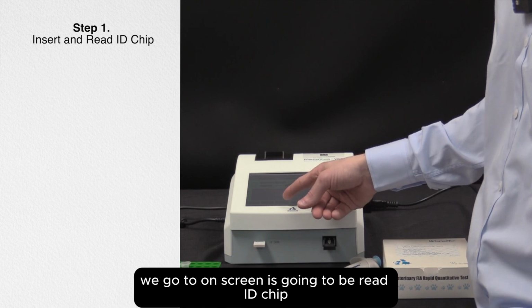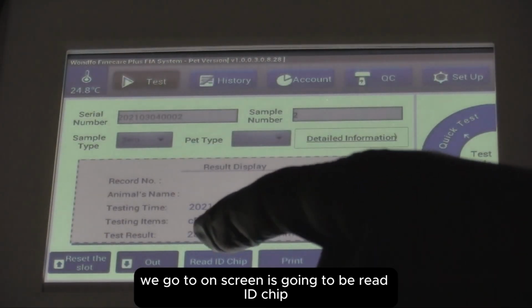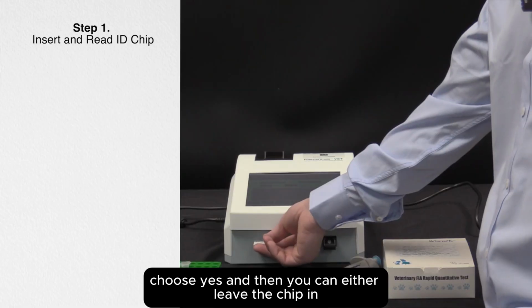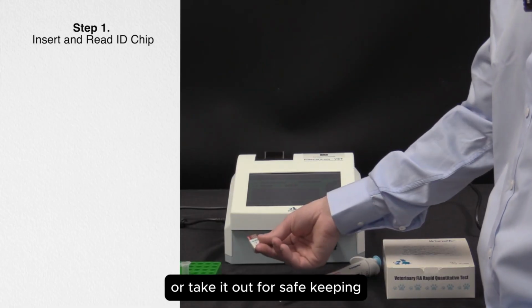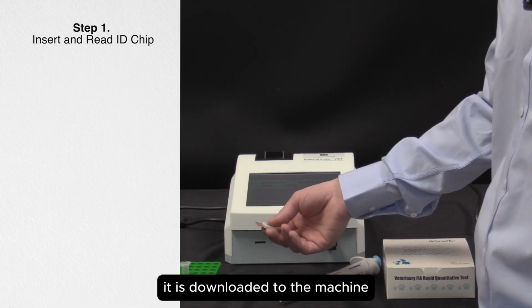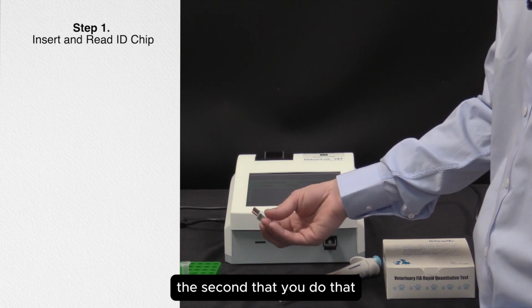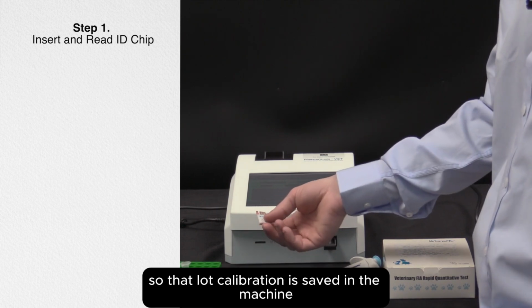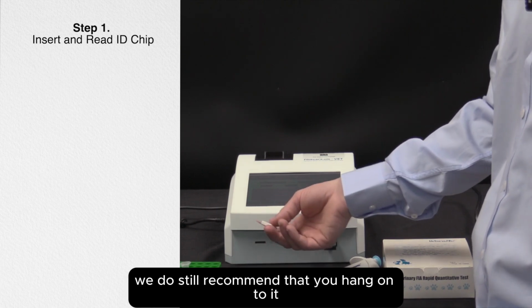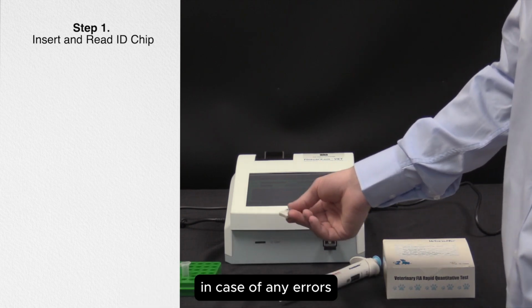Then the next step we go to on screen is going to be read ID chip. Choose yes, and then you can either leave the chip in or take it out for safekeeping. It is downloaded to the machine the second that you do that, so that lot calibration is saved in the machine. We do still recommend that you hang on to it in case of any errors.